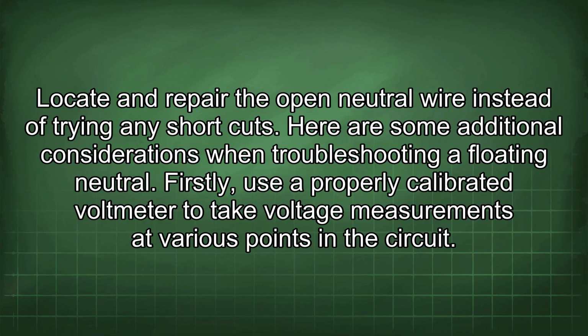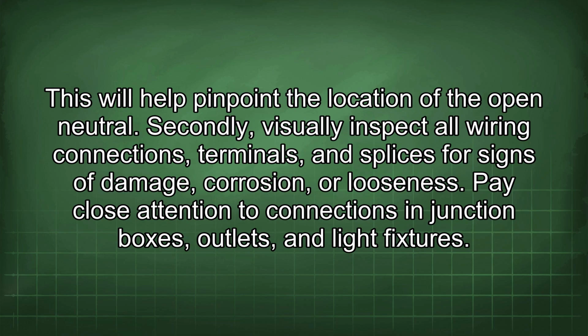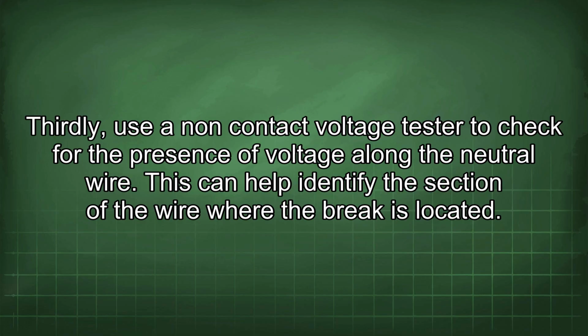Here are some additional considerations when troubleshooting a floating neutral. Firstly, use a properly calibrated voltmeter to take voltage measurements at various points in the circuit. This will help pinpoint the location of the open neutral. Secondly, visually inspect all wiring connections, terminals, and splices for signs of damage, corrosion, or looseness. Pay close attention to connections in junction boxes, outlets, and light fixtures. Thirdly, use a non-contact voltage tester to check for the presence of voltage along the neutral wire. This can help identify the section of the wire where the break is located.